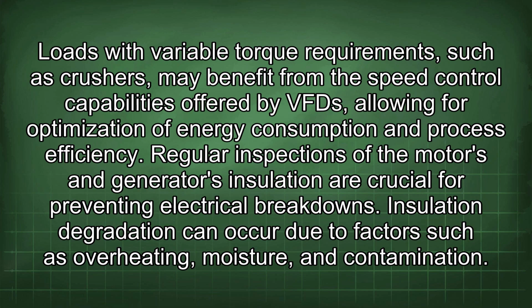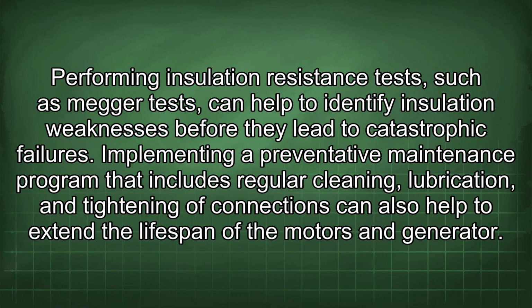Regular inspections of the motors and generators' insulation are crucial for preventing electrical breakdowns. Insulation degradation can occur due to factors such as overheating, moisture, and contamination. Performing insulation resistance tests, such as megger tests, can help to identify insulation weaknesses before they lead to catastrophic failures. Implementing a preventative maintenance program that includes regular cleaning, lubrication, and tightening of connections can also help to extend the lifespan of the motors and generator.